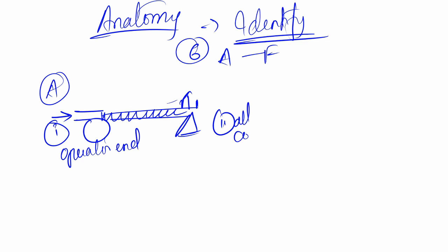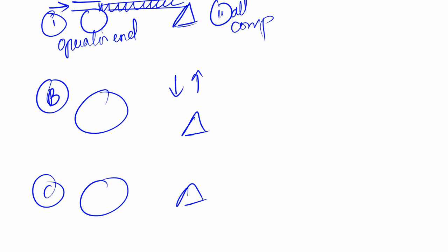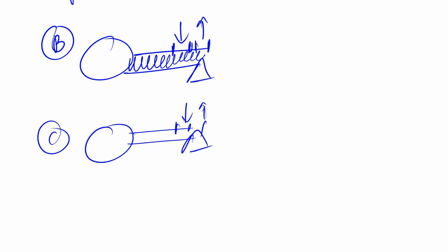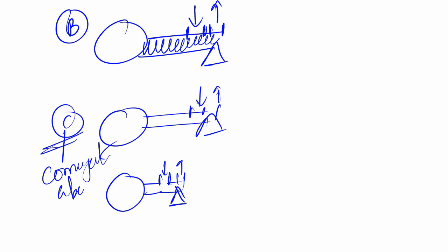Looking at B and C: both have a reservoir bag, a mask, and the fresh gas flow and outlet are near the mask. The difference is that in B there is a corrugated tube connecting the reservoir bag and the face mask, while C does not have one. So C appears smaller — it's essentially a smaller version of B.